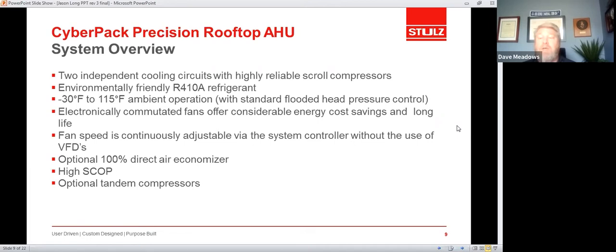These are located on both the condenser sections for air-cooled units and also in the supply air section of the unit as well. The Cyberpack units are available with 100% direct air economization. Everything is provided for the air side economizer with the exception of the exhaust or relief vent. We will control it, but that has to be installed in the building somewhere. The great benefit of the direct air economizer is that anytime the conditions outside are not too hot, too cold, too dry, or too wet, we can turn off all compressors and utilize the outside air to cool the data center.